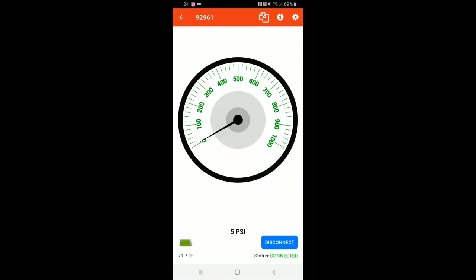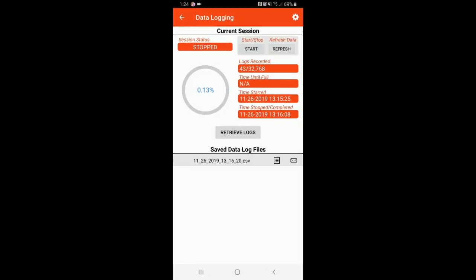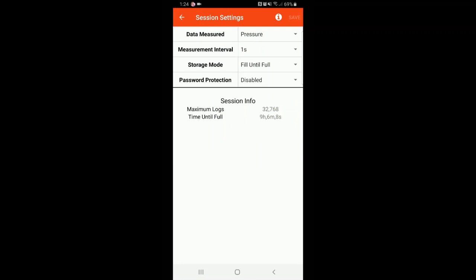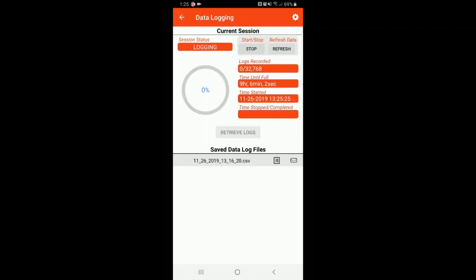Another feature of the application is the data logger tool. From the screen when you are viewing the transducer values, you select the double document tab in the top right hand corner, and this opens the screen relevant to all of the data logging settings. You have the ability to go in for data logging and change a number of different things. You can change the values in which the data is measuring. You can change the intervals, the storage mode, and whether or not this becomes password protected. You can create a data logger file by simply selecting the Start/Stop button here shown in the top center of the page. I have already begun this data logging session, and there is an indicator showing you exactly that. After you have had it run for the appropriate amount of time, you simply select Stop. After this, it will prompt you to remind you that these cannot be resumed after stopping. You simply select OK.